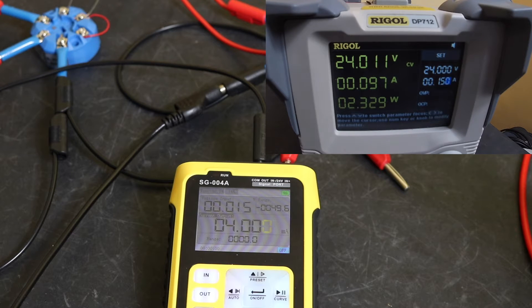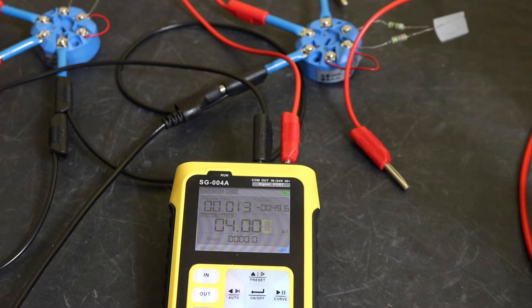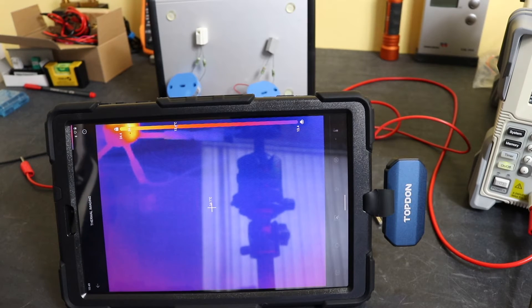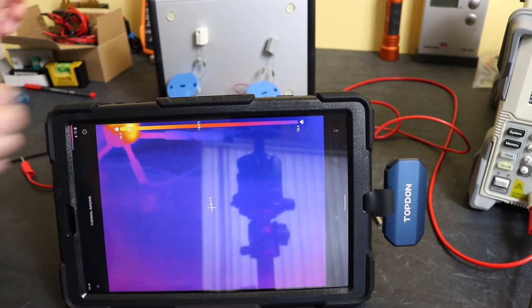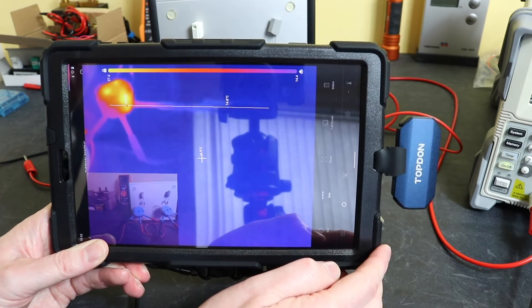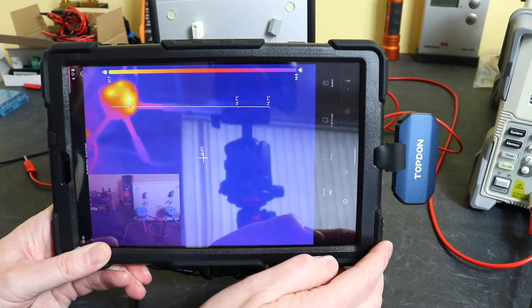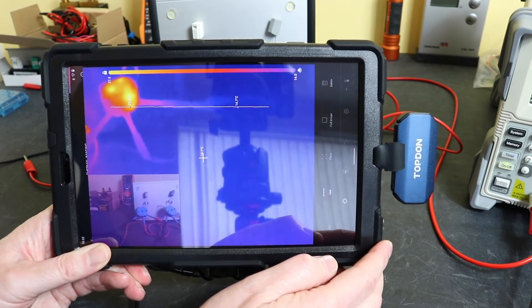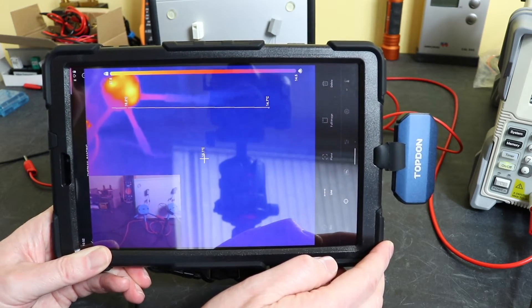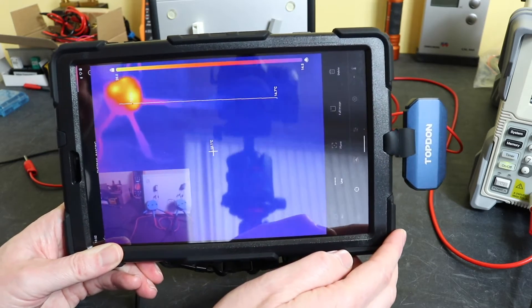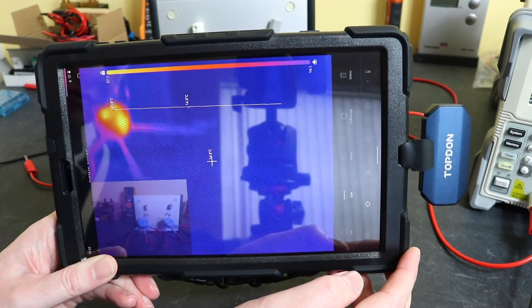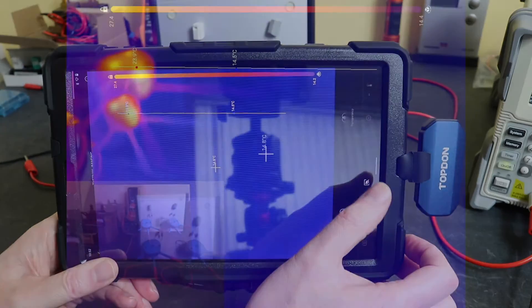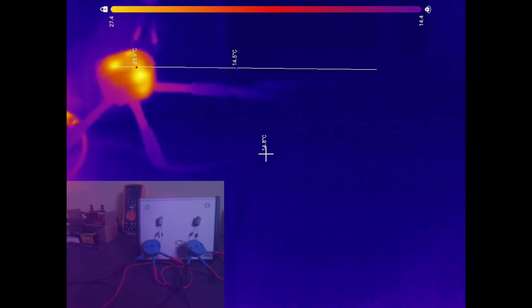I'll just do a quick rearrangement and I'll show you the other aspect that's telling me this has failed as well. So we've just rearranged everything and we've got a thermal imaging camera set up here. You can see the two units down here in the normal picture, there's the one on the left, there's one on the right. You see I'm running 27 degrees C on the failed one and the other one isn't even showing a temperature, normal ambient. I'll capture this and put this on the screen as well so you can see this for yourselves.